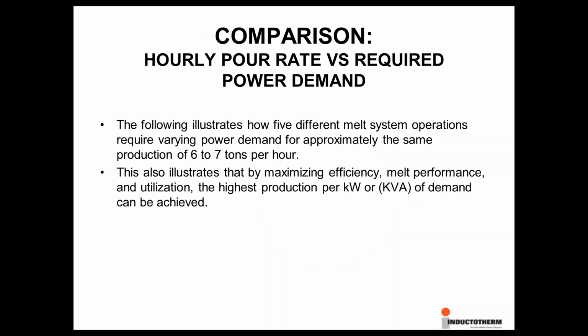In the next slides, I'm going to compare the hourly pour rate versus the required power demand for 5 different melt system operations, all producing between 6 and 7 tons per hour, all with varying power demands. This will illustrate that by maximizing efficiency, melt system configuration, melt system performance, and utilization, the highest production per kilowatt or per kVA demand can be achieved.